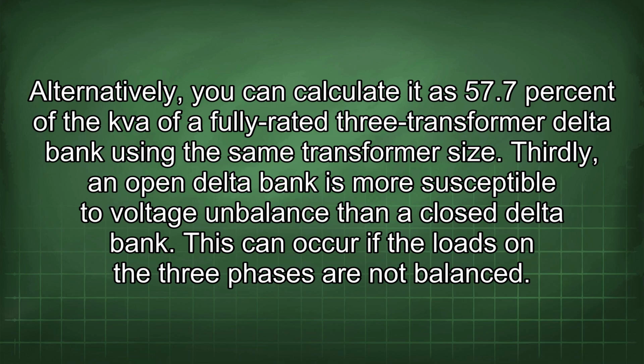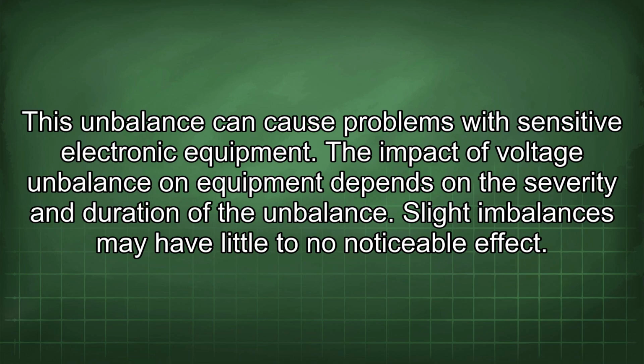Thirdly, an open delta bank is more susceptible to voltage imbalance than a closed delta bank. This can occur if the loads on the 3 phases are not balanced. This imbalance can cause problems with sensitive electronic equipment.